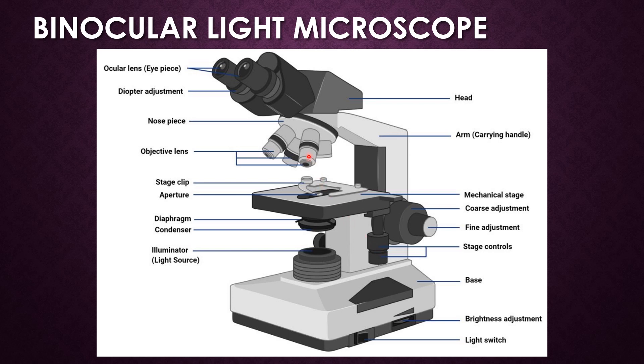The objective lens is directly present above the stage and is available in various magnifications like 10x, 40x, and 100x. When using the 100x objective, you must use immersion oil. Immersion oil is used to improve the resolution of a light microscope at high power — it has the same refractive index as glass, and when placed between the high-power objective and the glass slide, more light from the specimen enters the objective lens instead of being refracted away, resulting in a sharper, clearer image.